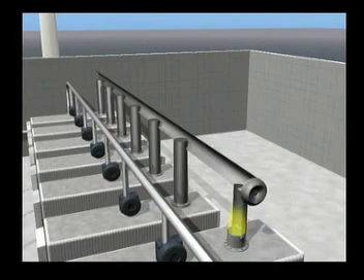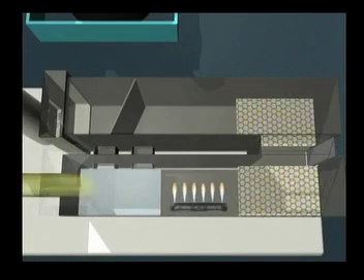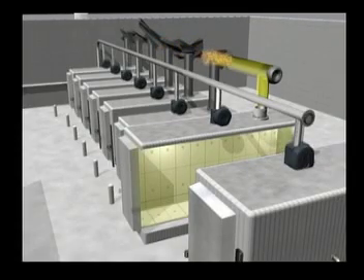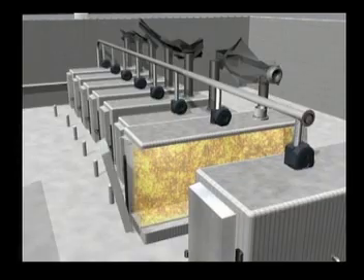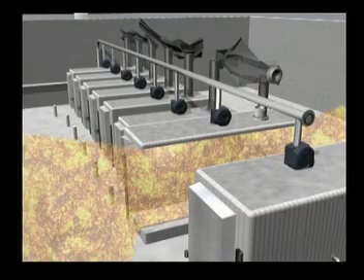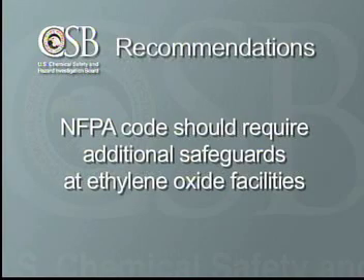Inside an oxidizer, fuel, air, and an ignition source are all present. There is a serious risk if the fuel-air mixture is too concentrated. Facilities with oxidizers should use multiple layers of protection, such as gas monitors, safety interlocks, and alarms, to prevent a single mistake from leading to an explosion.